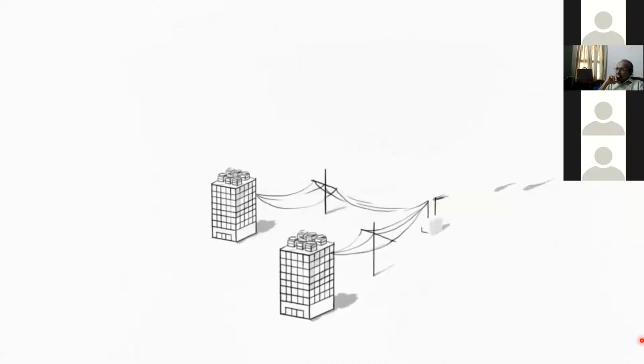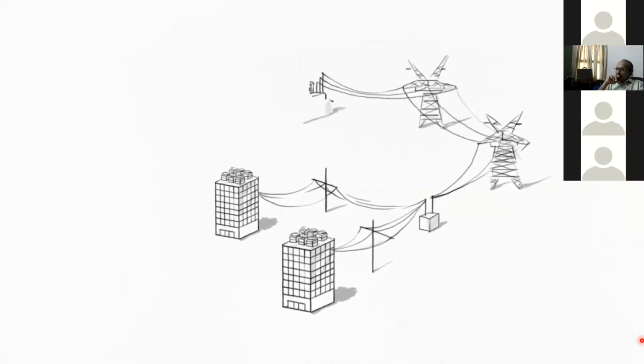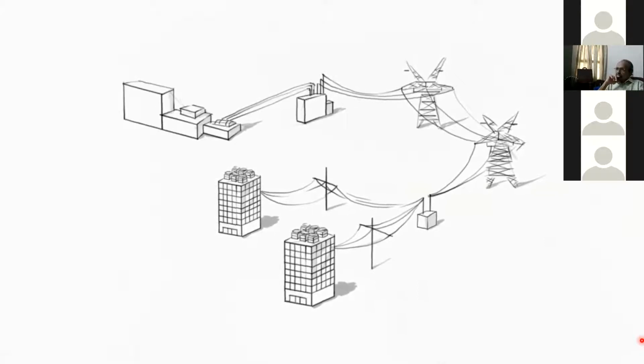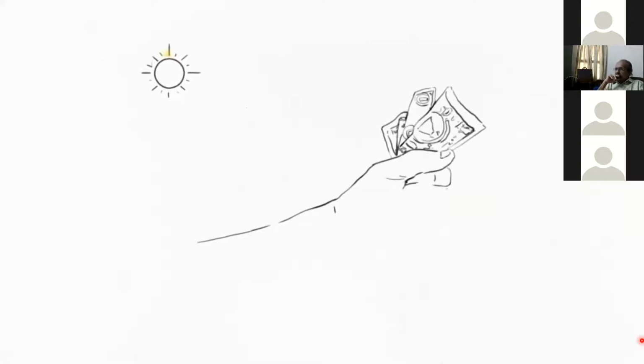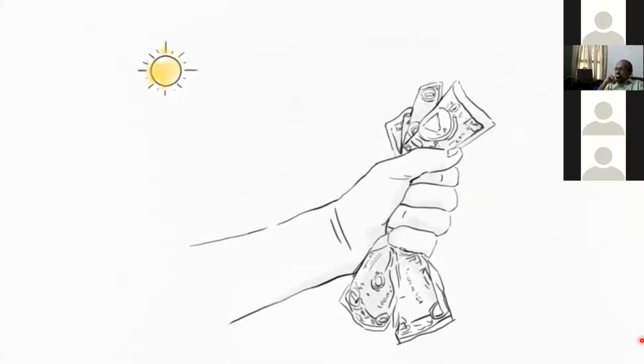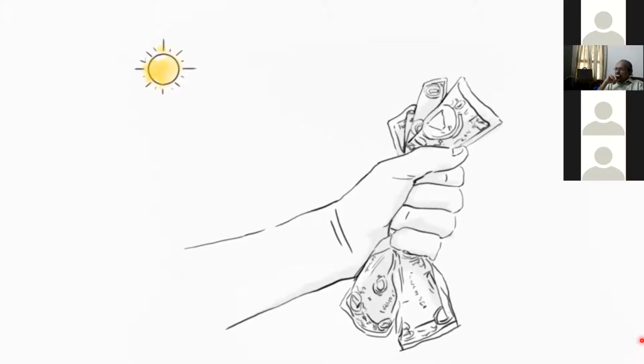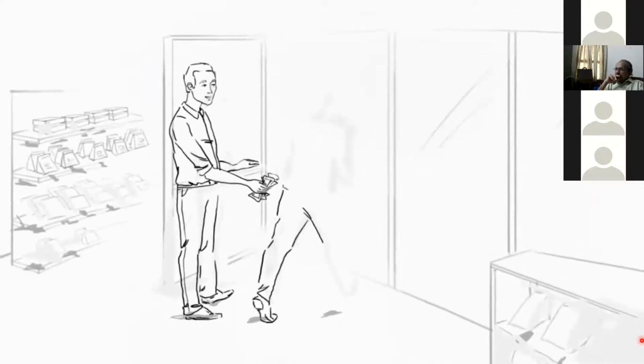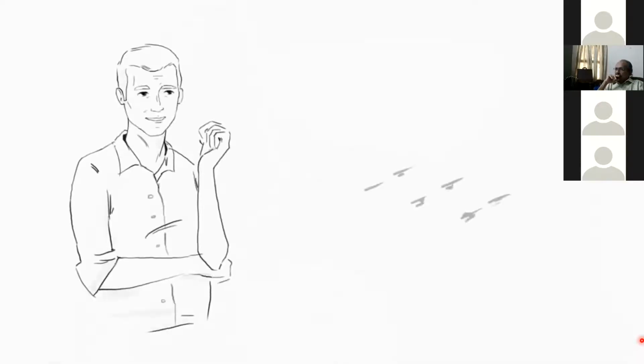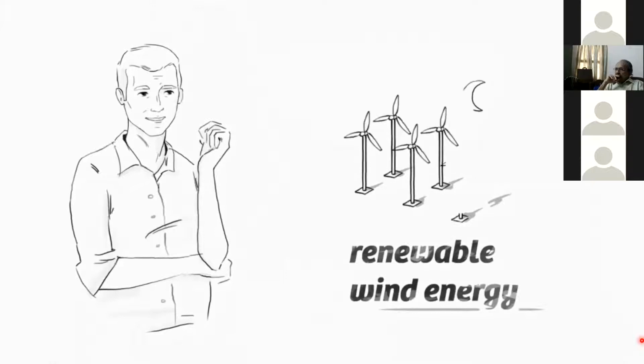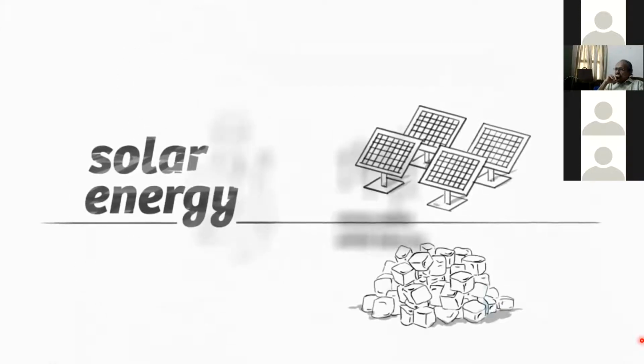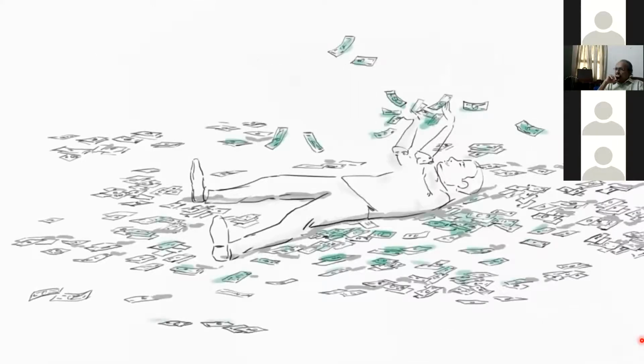Storing cooling ahead of when you need it not only reduces energy costs, but can even generate income through what's called demand response. When the grid is overtaxed during the hottest periods of the day, some grid operators will actually pay you to reduce power usage during the day. That's like the grocer paying you to take the ice before the party. You can even feel great about ice storage because at night you can store renewable wind energy from the grid. Have solar? Stored cooling can kick in when the sun's not shining. So now you're not only rolling in the green, you're being green too.